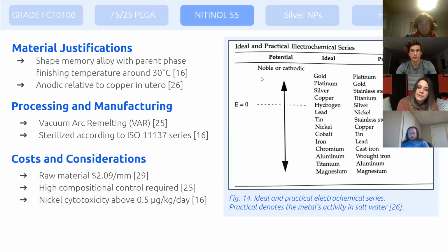Nitinol 55 is the primary metal for the device frame. The device's shape memory component is crucial, and the superelastic behavior observed in utero will successfully counteract intrauterine compressive forces between 1 to 7 newtons. Such compressions are common immediately after device insertion as the uterus attempts to expel the device. Our device has shape retention abilities in spite of these forces to create a safer user experience, in addition to offering a transverse width that more closely matches uterine width at roughly 24 millimeters. Oversized devices like the Paragard often rotate 90 degrees in utero.